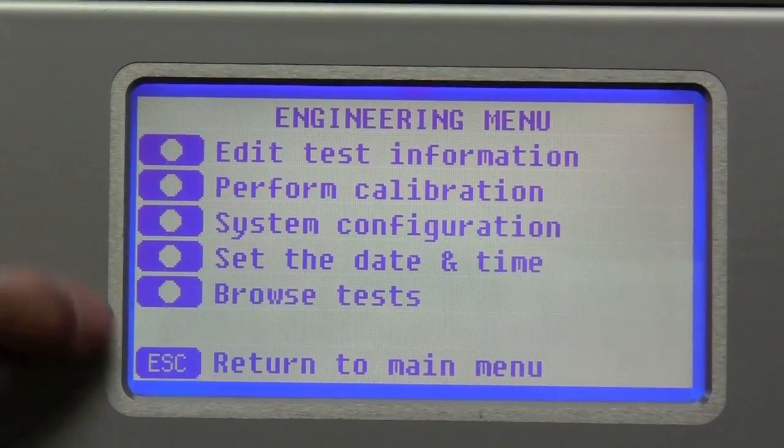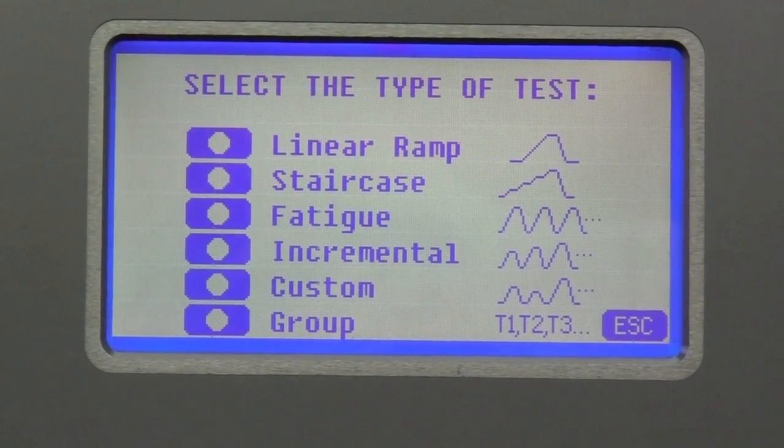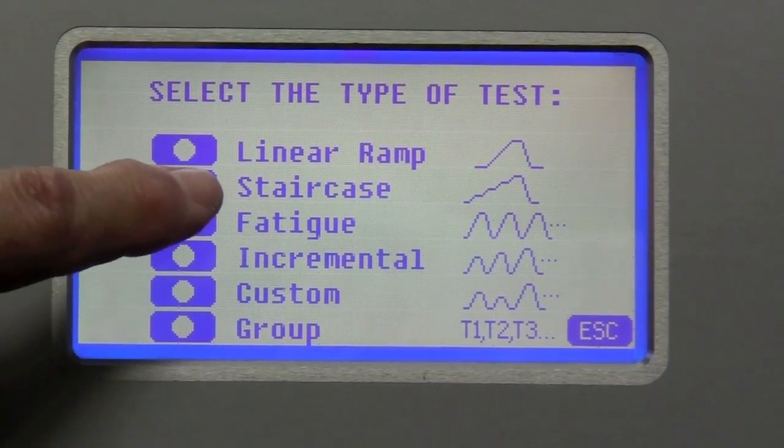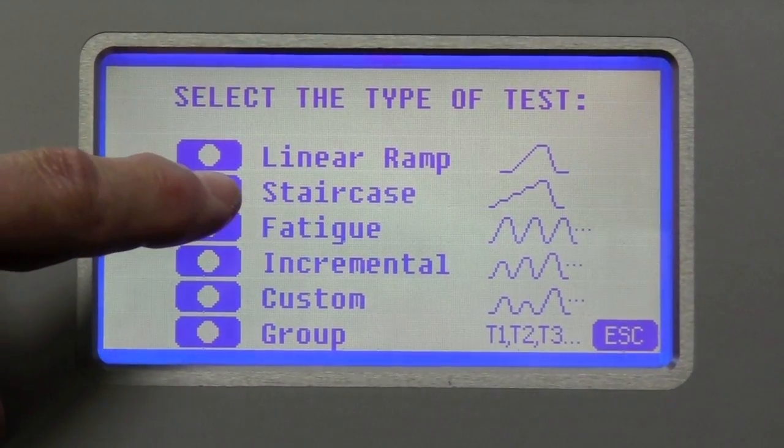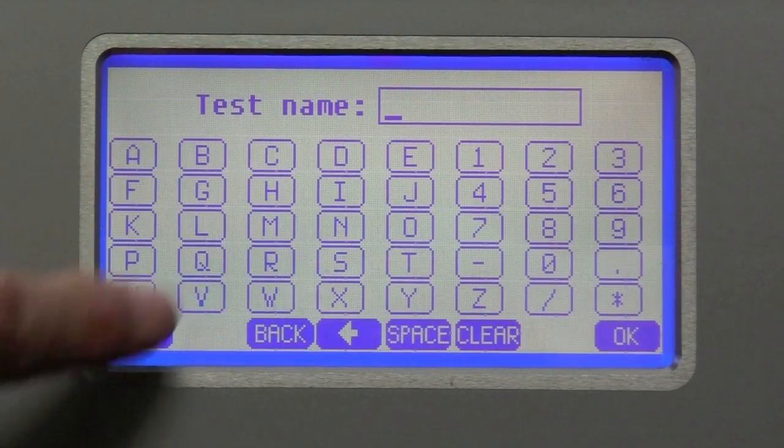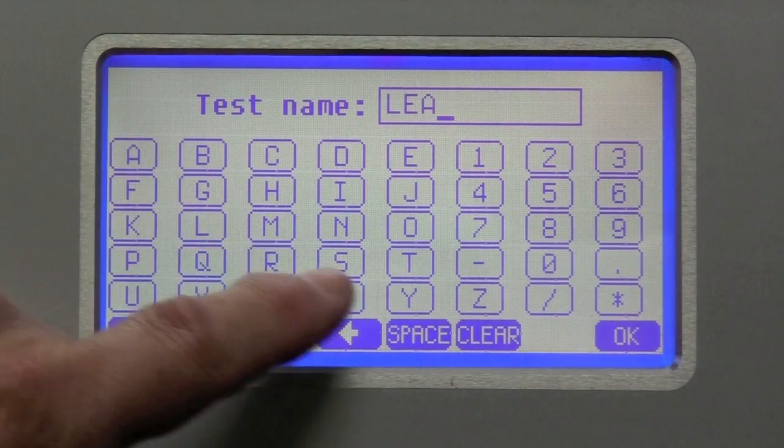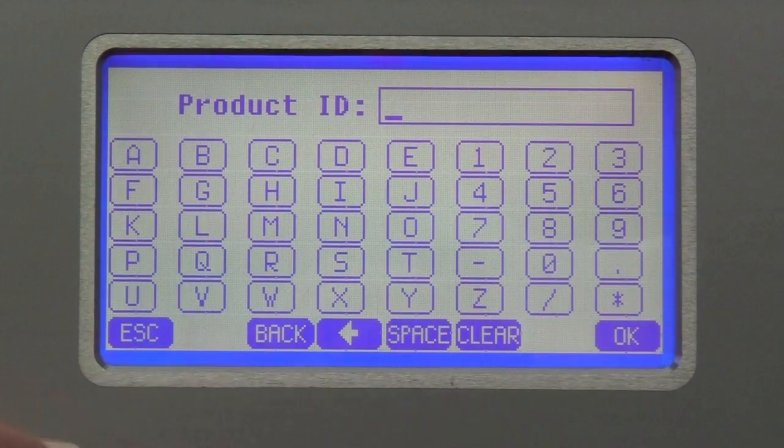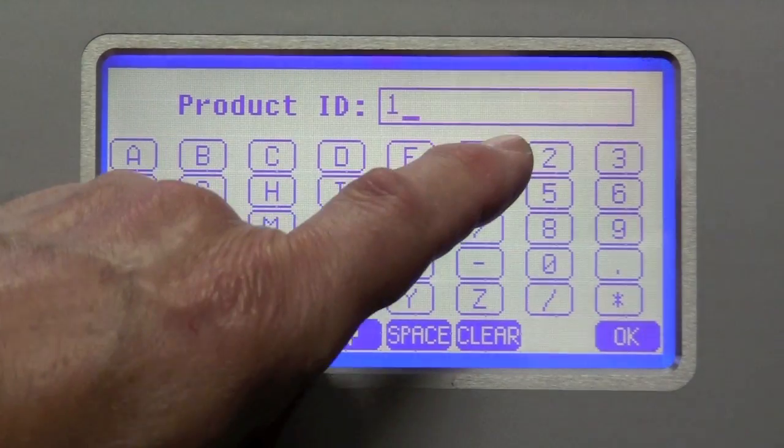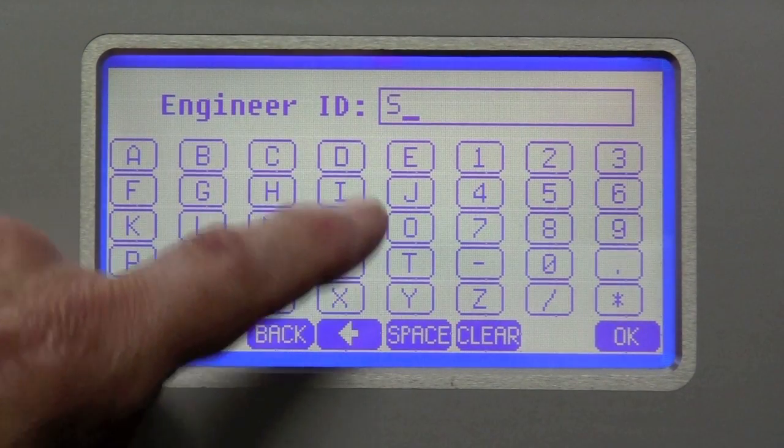I'm going to the engineering menu, to the edit screen, hit the new button, and I'm going to use the staircase test. In this case, I'm going to use PSI and I'm going to call this a leak test. And then the product ID is 123. And I'm the engineer.